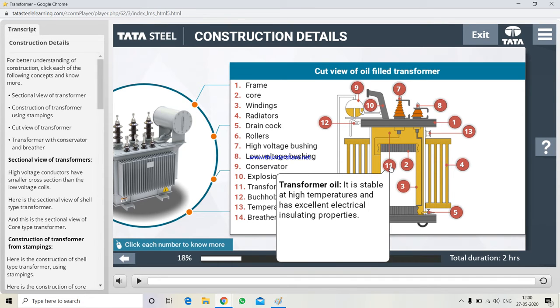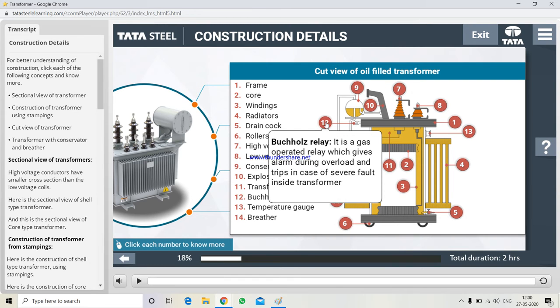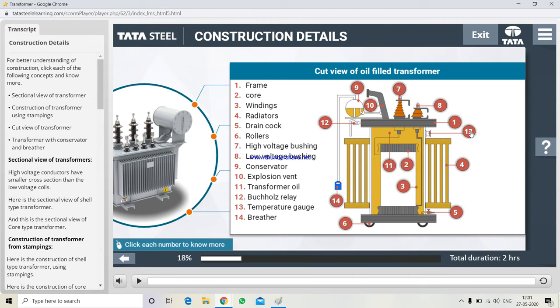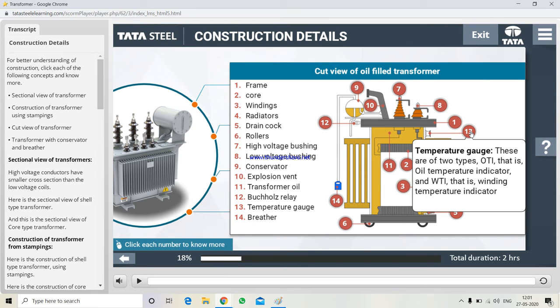Transformer oil. It is stable at high temperatures and has excellent electrical insulating properties. Buchholz relay. It is a gas-operated relay which gives alarm during overload and trips in case of severe fault inside transformer. Temperature gauge. These are of two types, OTI, that is oil temperature indicator, and WTI, that is winding temperature indicator.